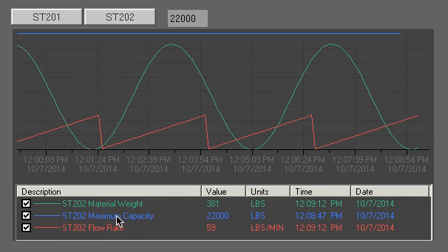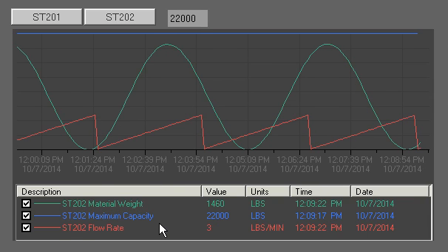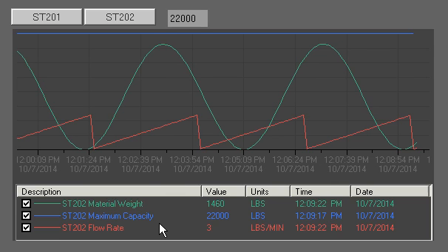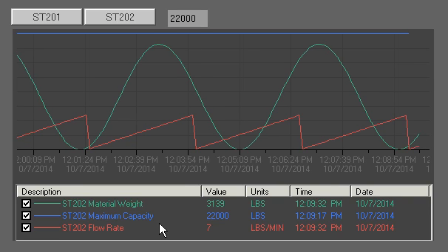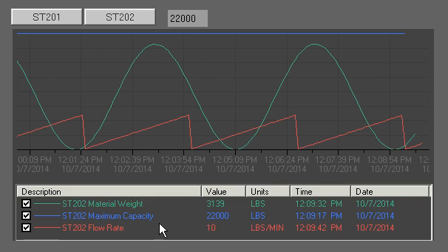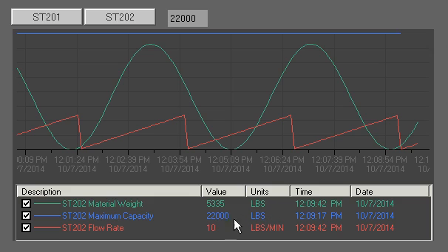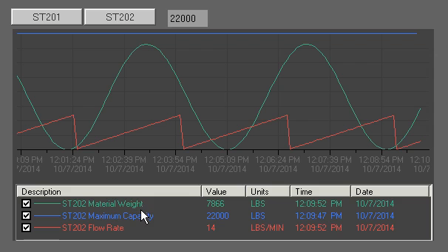So the new piece here is the maximum capacity signal. What that signal represents is a calculated value. That value is calculated on a periodic basis using the data that is imported from an Excel spreadsheet for the tanks, with all the settings, into a SQL database, and it's using the SQL database configuration to calculate the value based on a given tank and the material that is assigned to this tank, and all the attributes of that tank, obviously, and the density of the material.